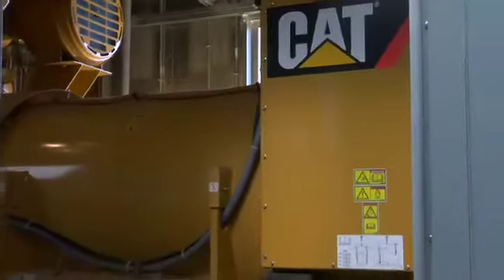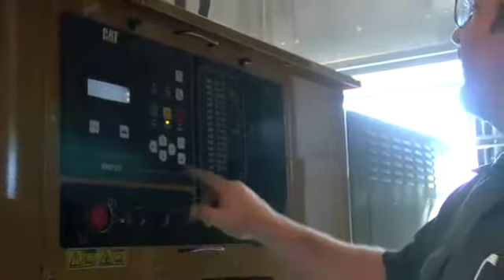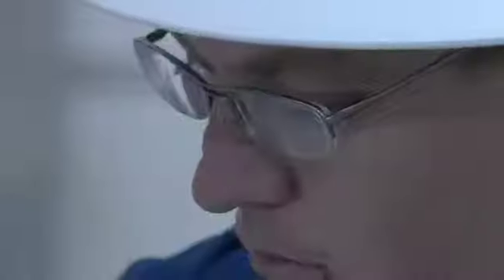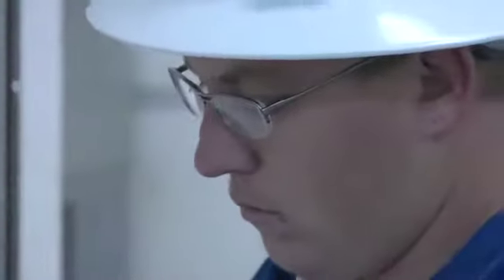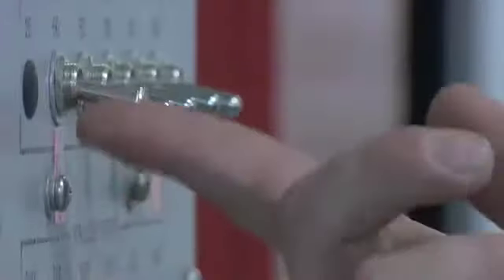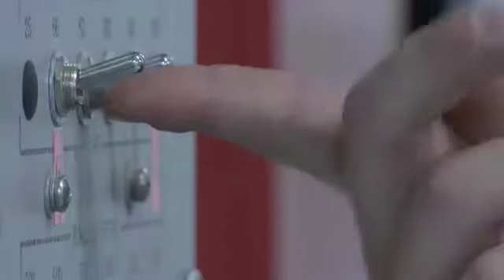What types of inspections do you do, and how often? Let me give you an example: our generators. We inspect them weekly, run them monthly, and each quarter we put a full load test on them. We have an in-house load bank that allows us to do this, ensuring our generators are in proper operating order when an emergency arises.